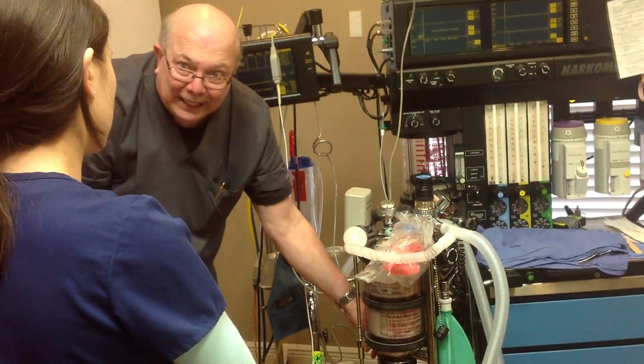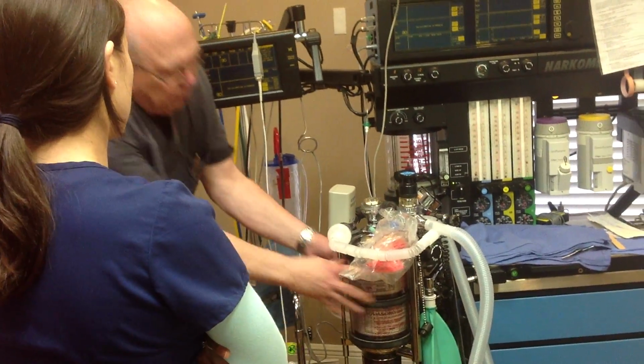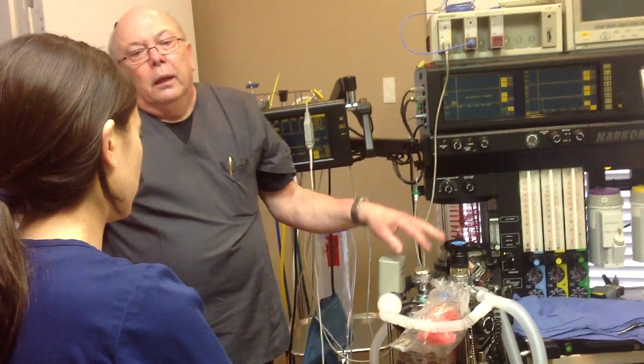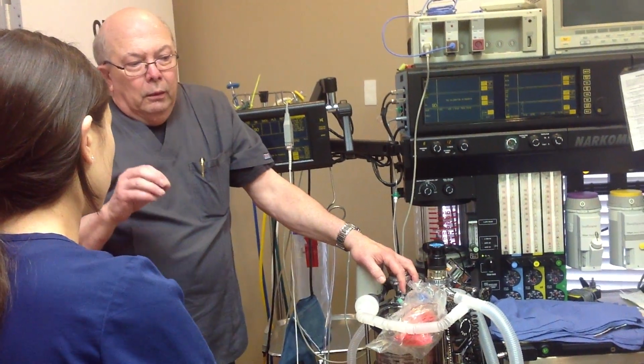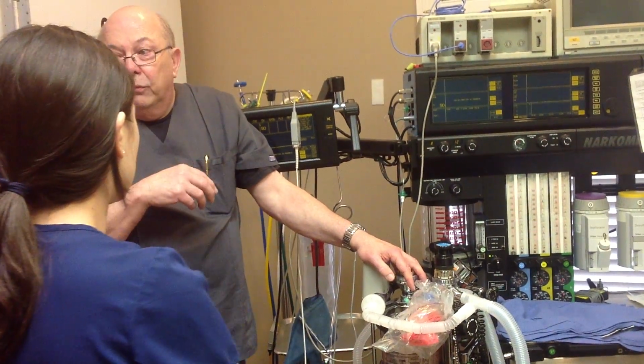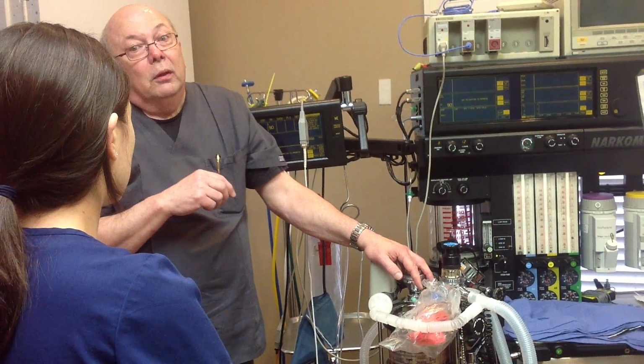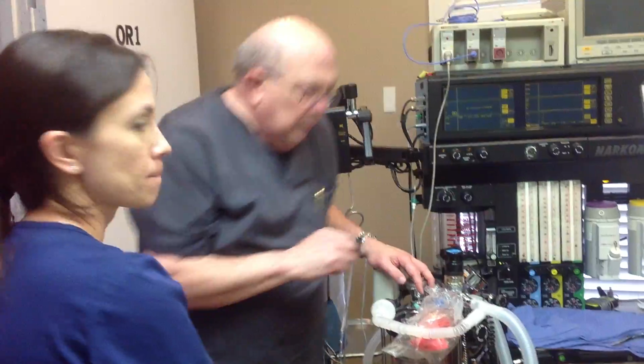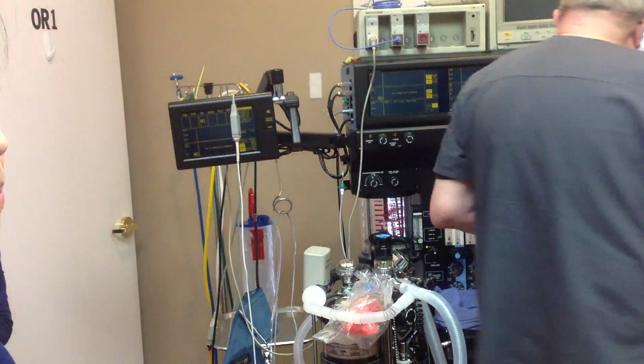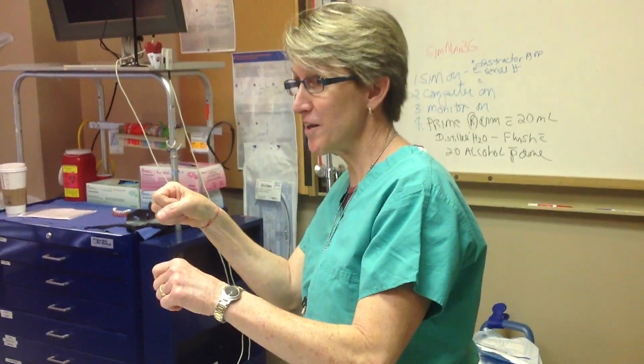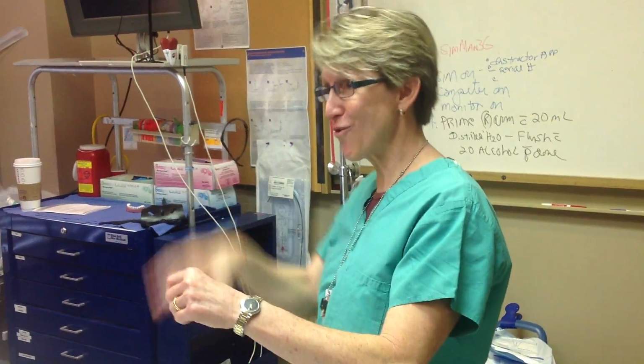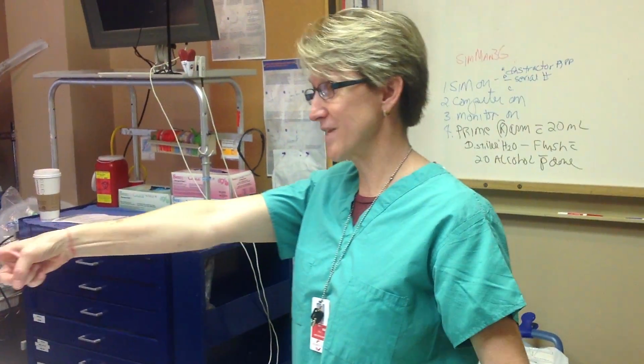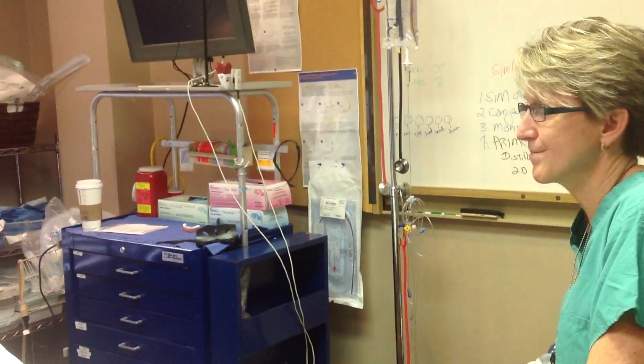Reseal it, and you should hear that click, okay? And then you can maybe check it again. Now what will happen a lot of times is the people that clean your room up may change it for you. And so you need to make sure that it's sealed. That's another frequent place that, when your ventilator doesn't work and you can't get air into your bellows, that's what's happening. Your CO2 absorber is not connected firmly, or it's leaking. So you're ventilating, but you're not getting air, and your bellows doesn't go up and down. Sometimes that's a frequent place that happens.